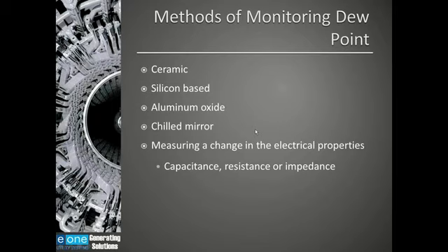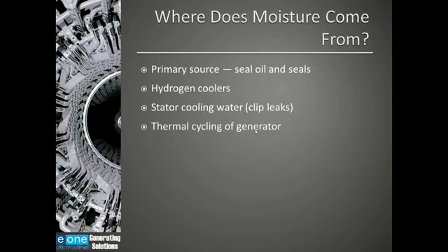Years ago, multiple manufacturers had clip problems, and this is where the water transferred into the winding, and these clips would leak, and they could add moisture to the hydrogen. And then the importance of thermal cycling of a generator. Again, this will not create moisture, but it can create condensation to form on components inside the generator.